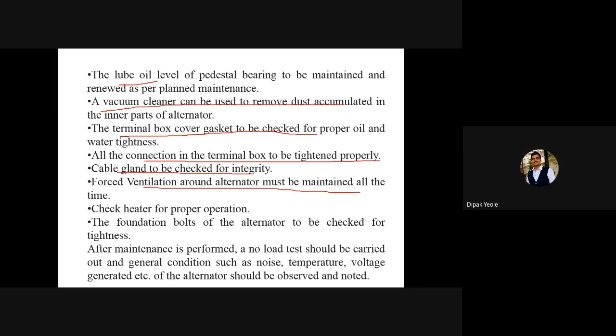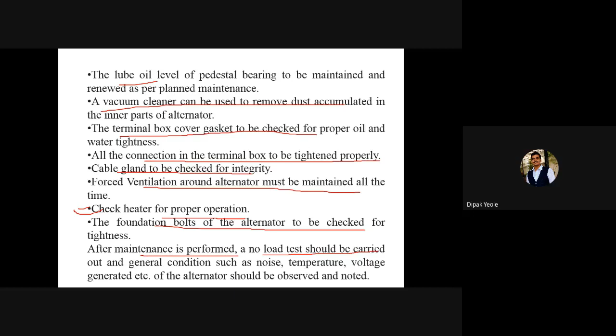The foundation bolts of the alternator are to be checked, and after the maintenance is performed, a no load test should be carried out. Because after doing the maintenance, our work is to check the machine by application of voltage or current, and if it gives a satisfactory result, then you can say that the machine is okay for use. Now we are interested in the insulation parameter, and we know that insulation plays an important role inside electrical machinery.